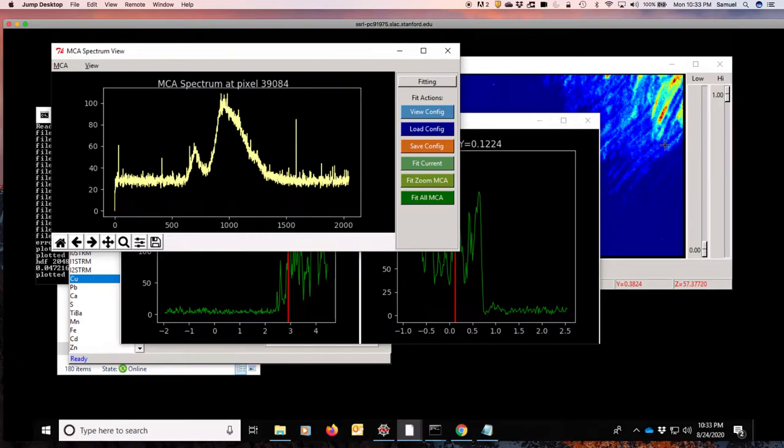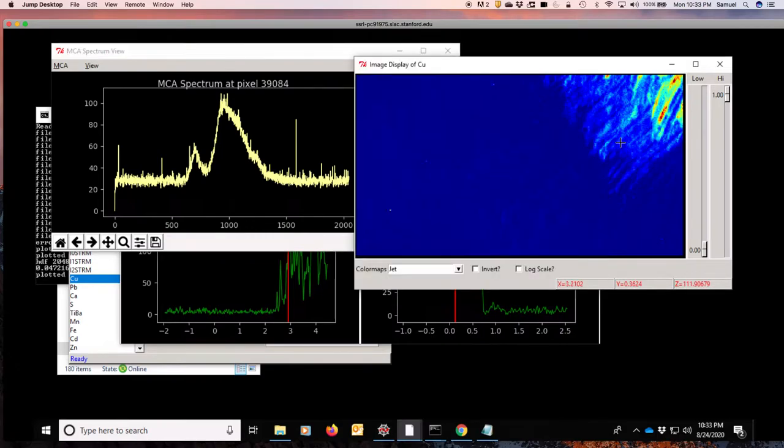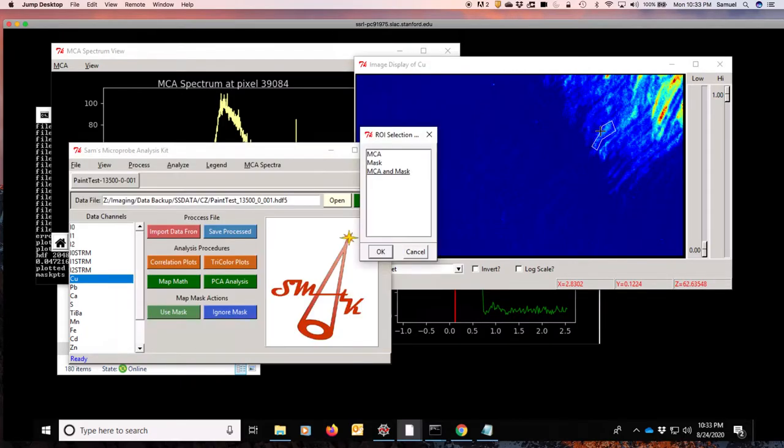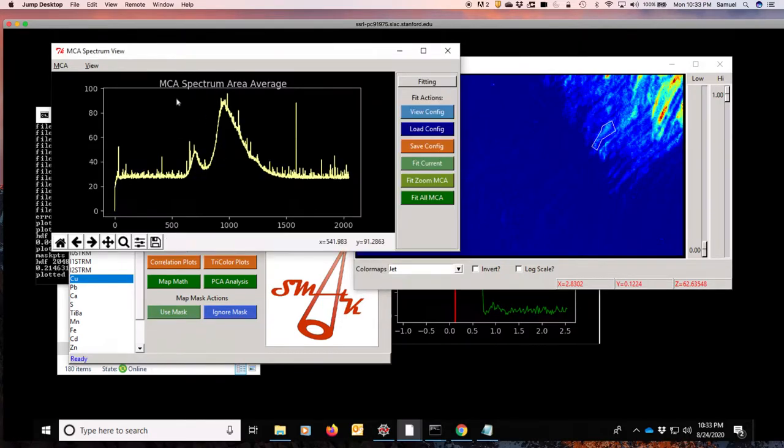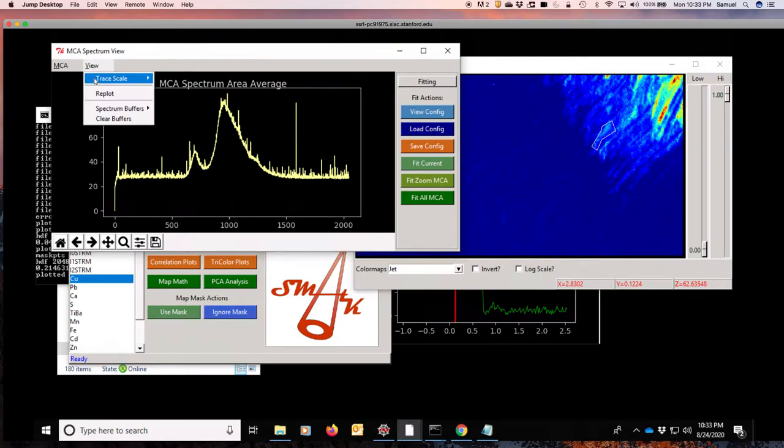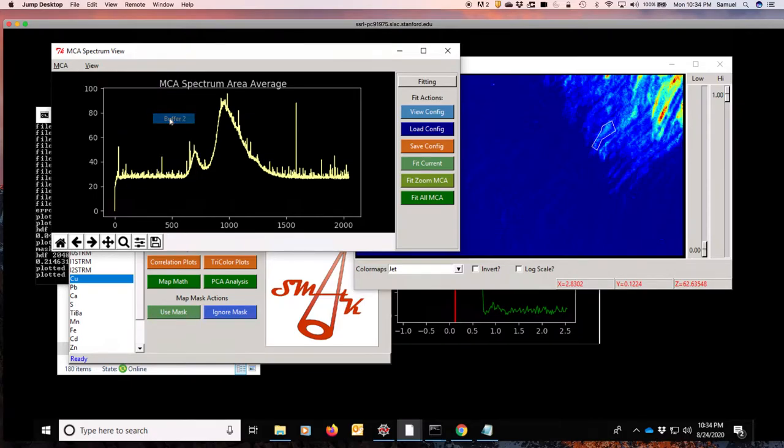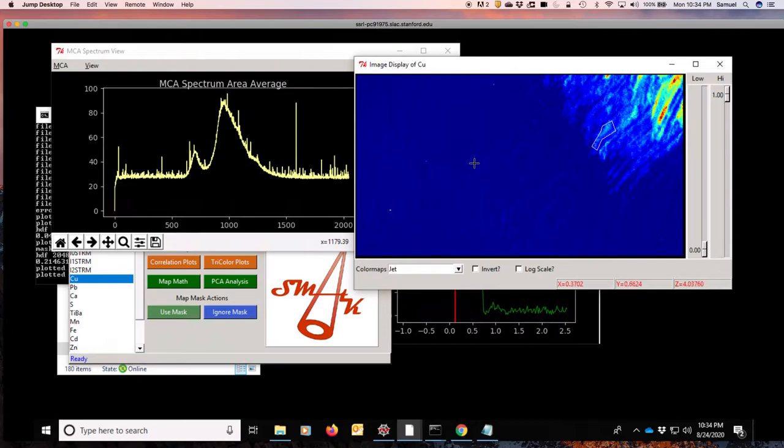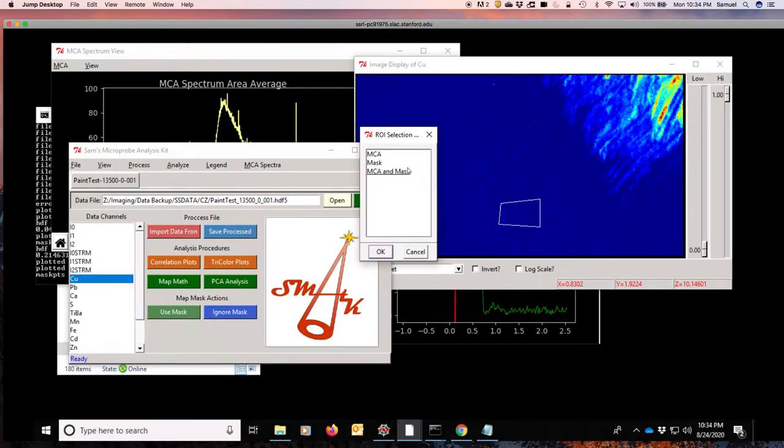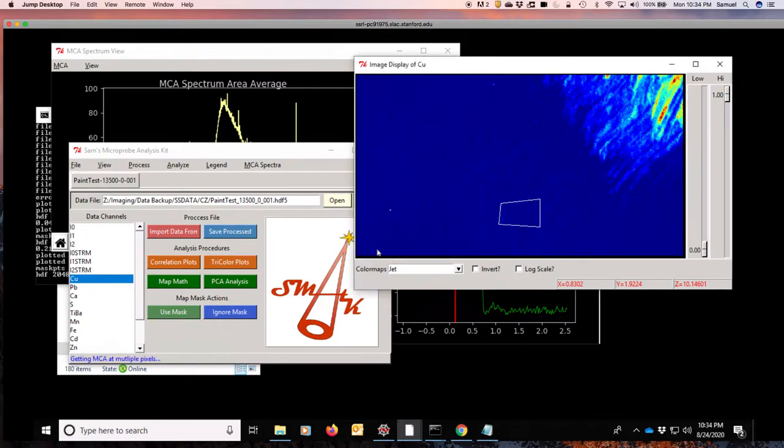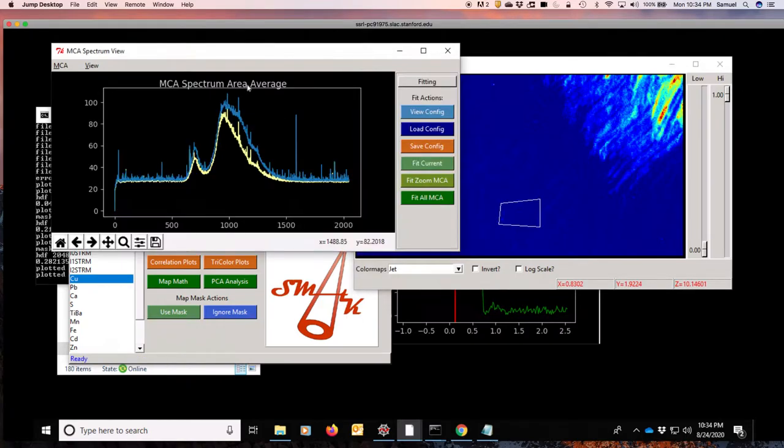So we can average several pixels together by using the shift key to select an area and say, what does the spectrum look like in this particular area by saying MCA here? And that creates a slightly smoother spectra because it is averaging several. And we can do the same tricks with saying, let's put this into a buffer and now go to buffer two and compare the area that is down in this section. And we say MCA there. And now we can look at the difference between two different areas.